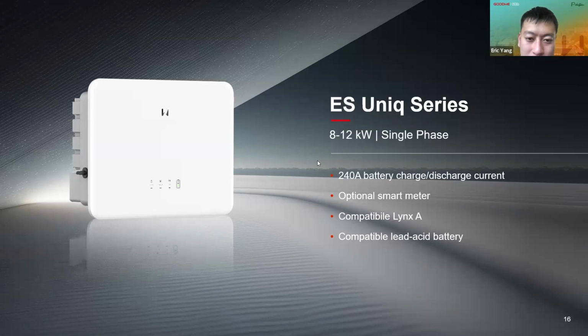Okay, there's a question about the temperature. They are living in a city where the temperature is normally around 50 centigrade. So will it affect the efficiency of the device? If the environmental temperature is 50 degrees, we think it will derate. But the derating does not depend on the environment temperature, it depends on the internal temperature. So maybe you can install a fan beside the inverter, and also install it in an environment where the temperature is not high, so the inverter does not derate.